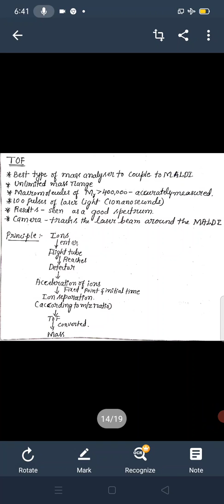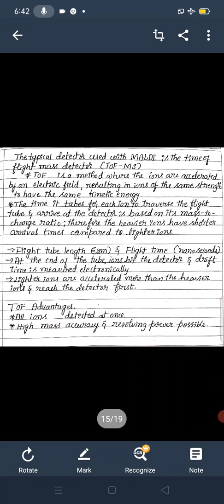Commonly, a few hundred pulses of laser light of nanosecond duration are applied, and the information is collected to get a resolved spectrum. The laser light is monitored on the spot of the sample by means of a camera which records flashes. Let us know about the advantages of time of flight. Here, by using this TOF, all ions are detected at once, and it gives high mass accuracy and resolving power.